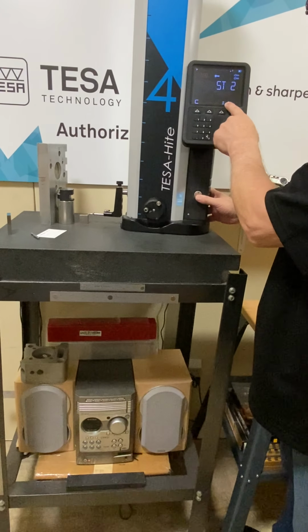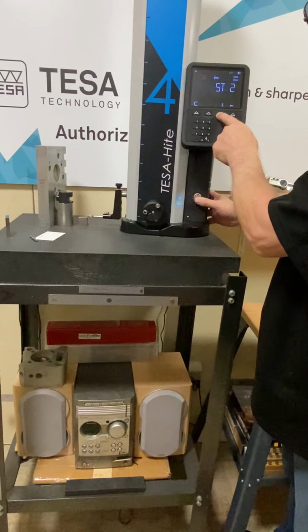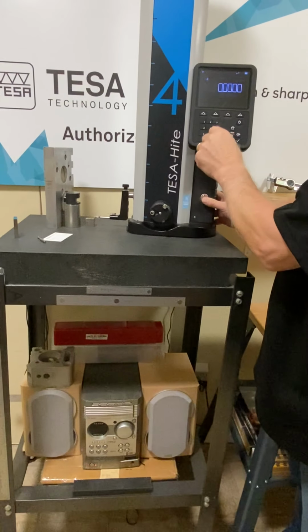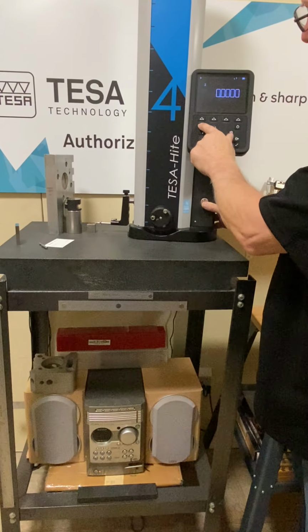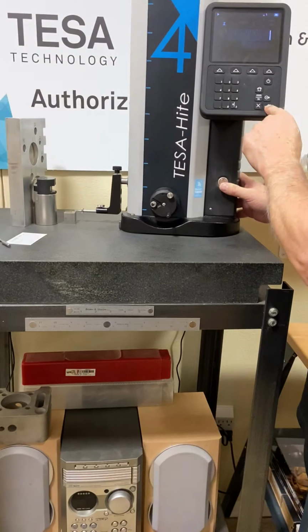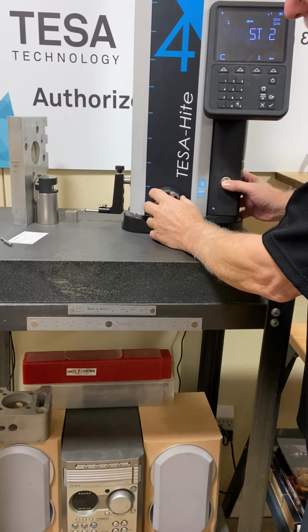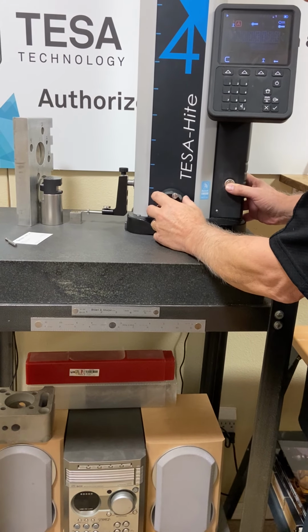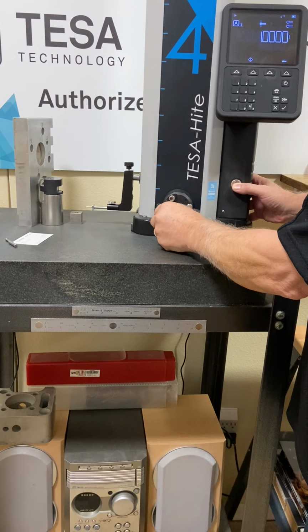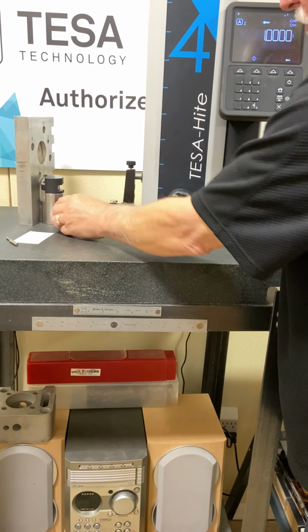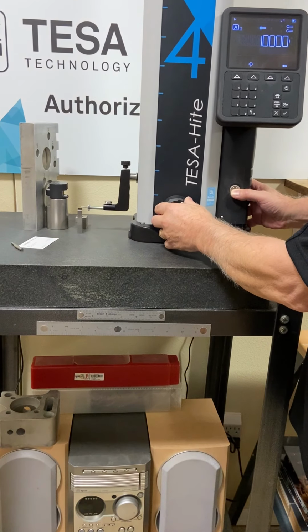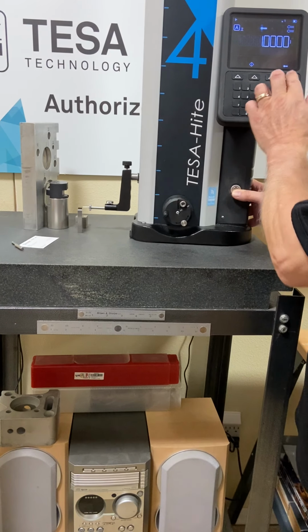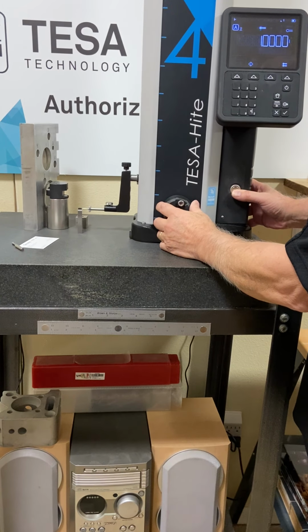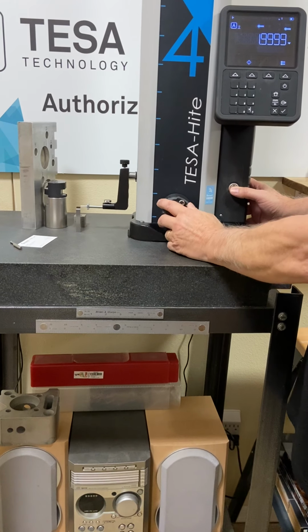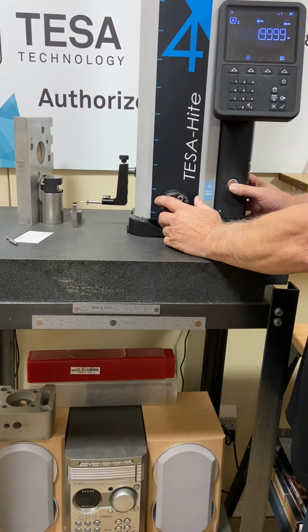So I hit my indirect reference, the symbol's right there. I hit the button below it, and this allows me to key in a number. I'm going to put in the number 1, and I'm going to hit the check mark to enter it. And I come over here, take a probe hit twice as I'm establishing my datum point. So now I've got my surface plate set at 0. So when I hit on this 2-inch gauge block, I'm going to just be short of 1/10 of 2 inches.